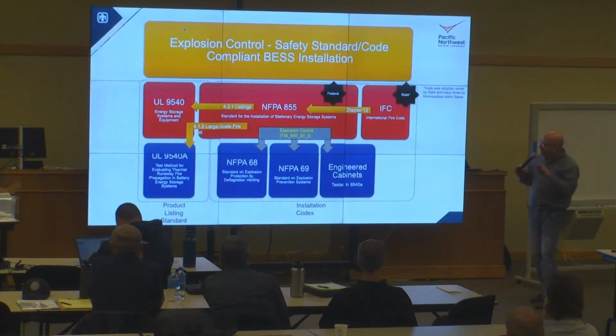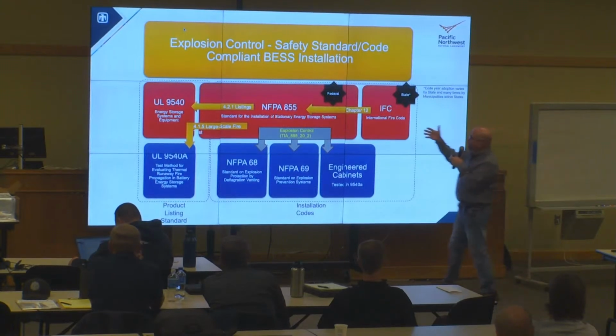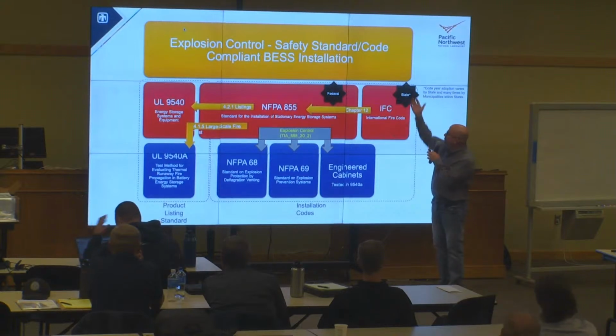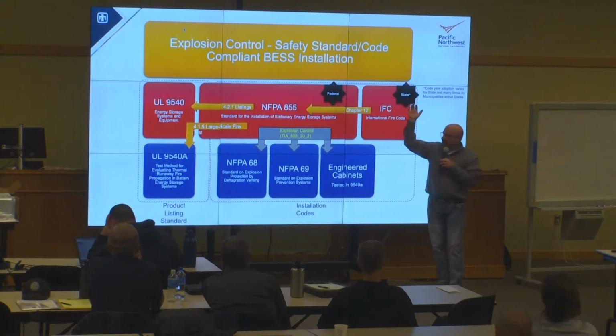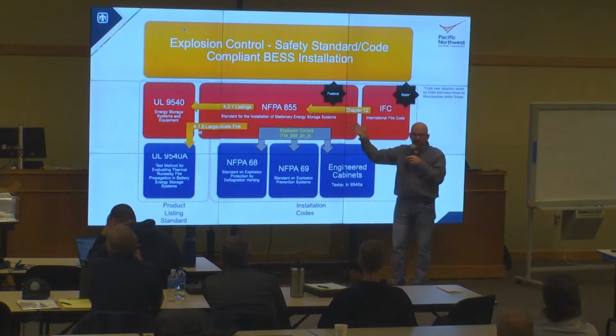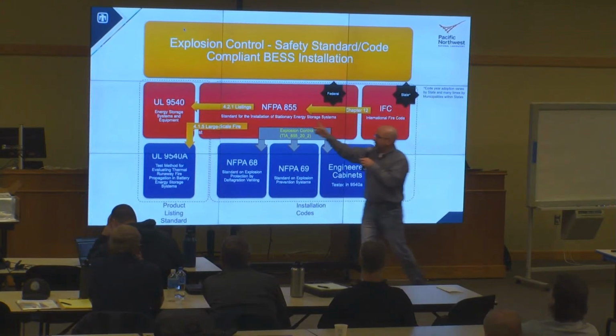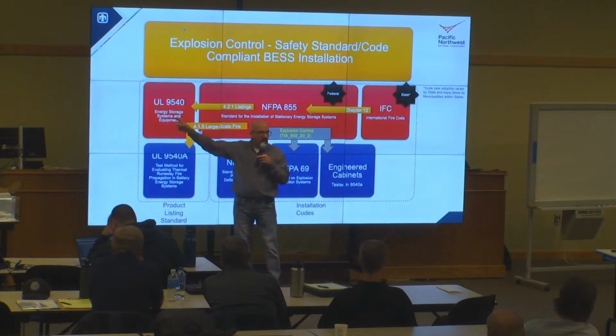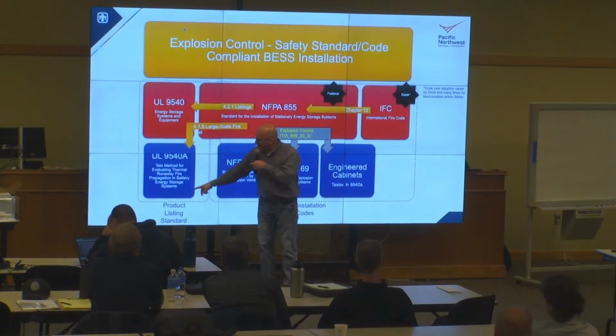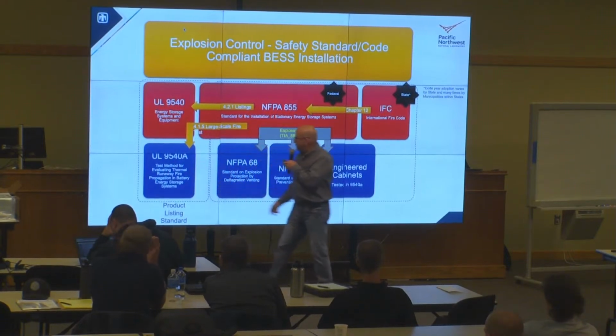Okay, this is kind of a busy slide, but this is really important. When we talk about explosion control, we have two main codes. We have the International Fire Code, which is adopted by most states. Then we have NFPA 855, which is only adopted by about 5 states, but most federal facilities follow it. Both of these require listing to 9540, right? So we're telling everybody it's got to be listed 9540 and 9540A. So that's part of the product standard.